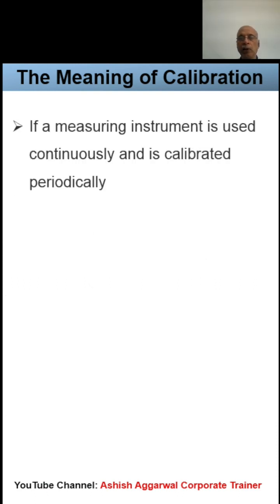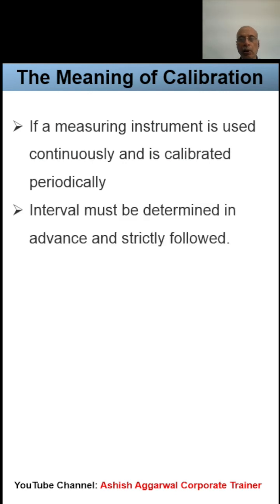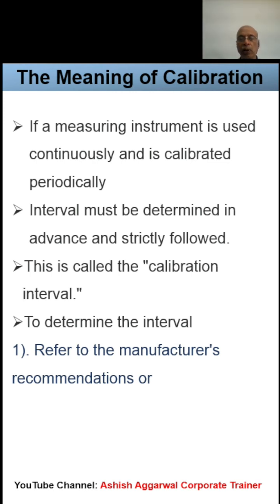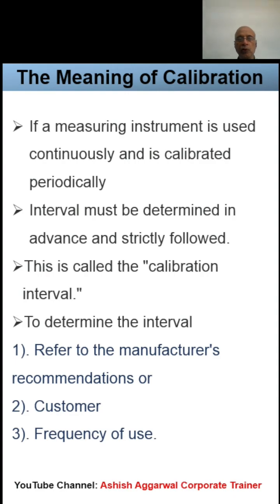When we are using the measuring instrument on a continuous basis, the instrument is required to be calibrated periodically. This period of calibration is required to be determined in advance and it must be strictly followed. This is called the calibration interval, which can be decided as per the recommendation by the instrument supplier, by the customer requirement, or by the frequency of use.